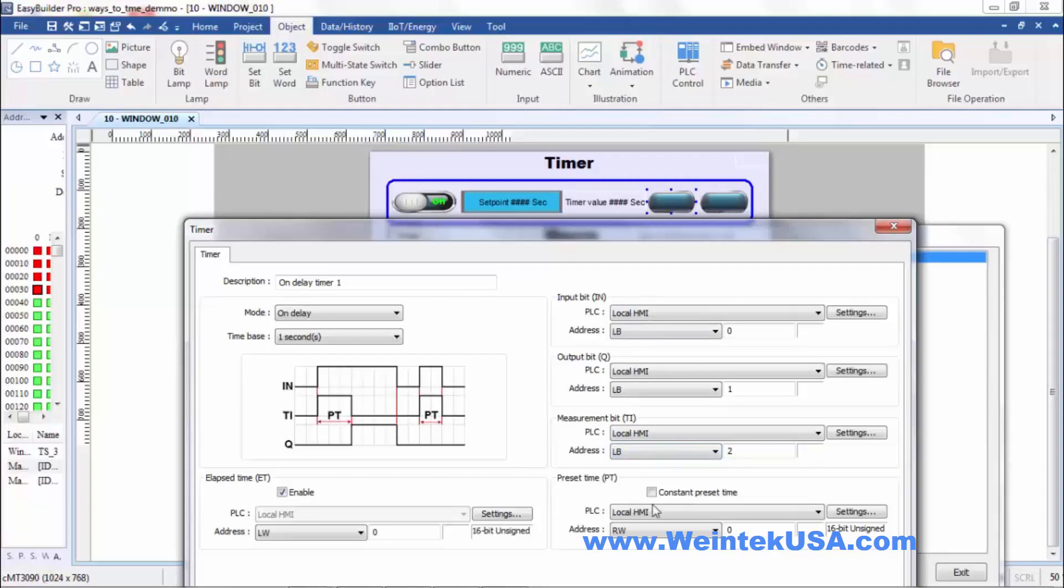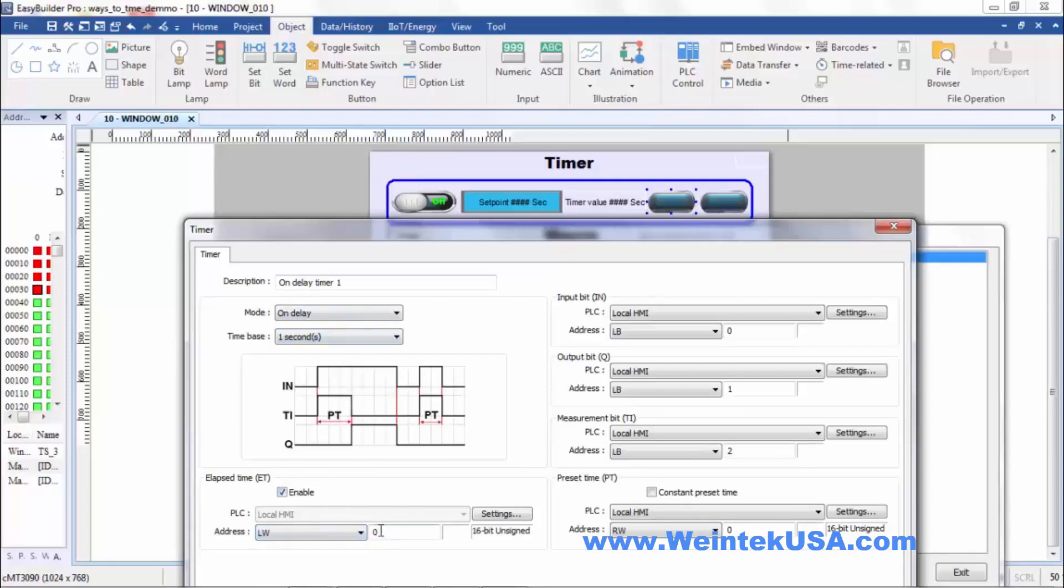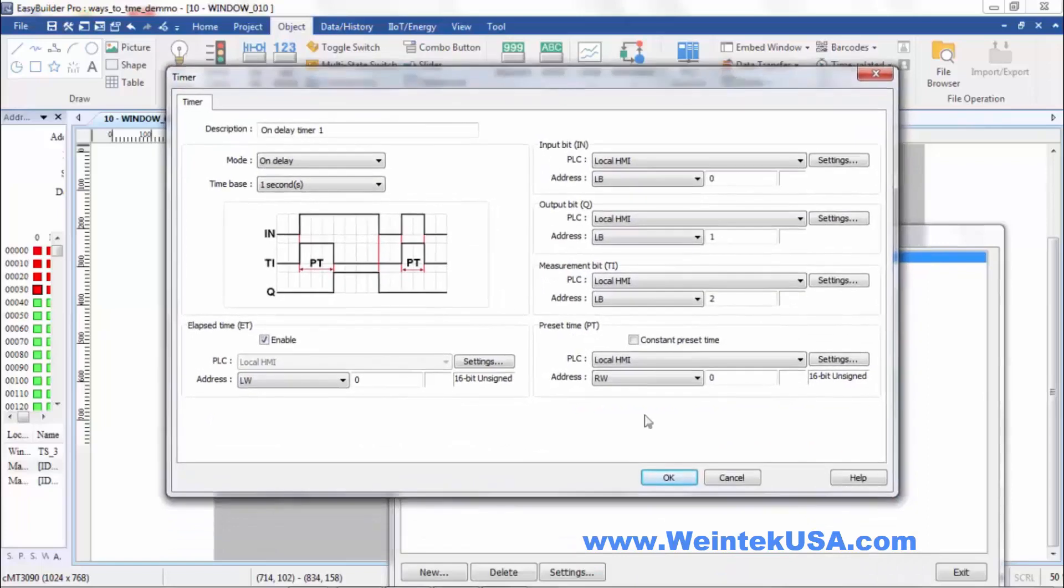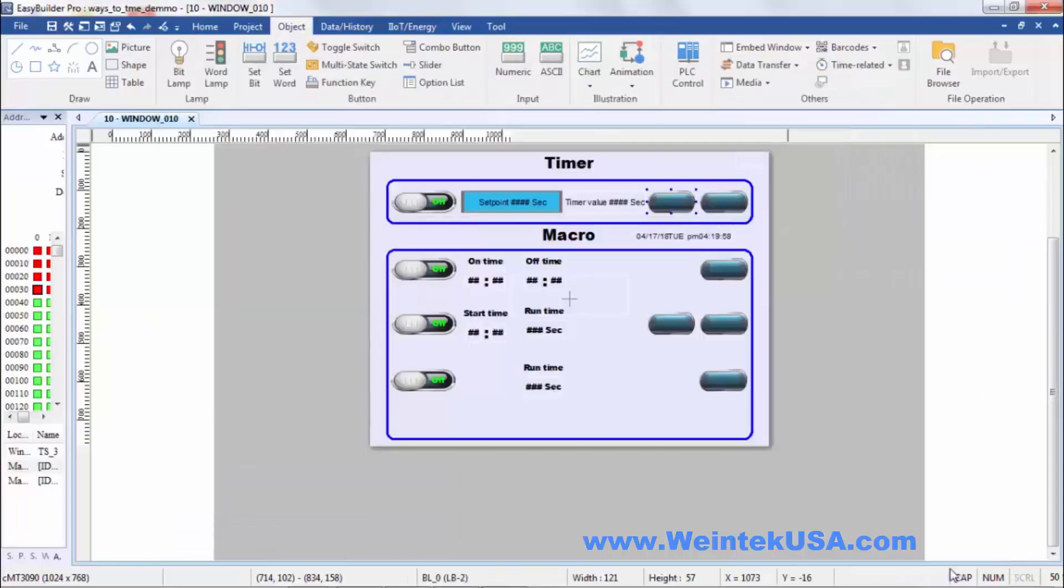We've got our preset register. We could either do a constant time base or a preset. I've chosen RW0. And then we've got our accumulated time register. That's where we place our elapsed time within our timer while it's timing. And I've chosen LW0. Go ahead and OK out of this.